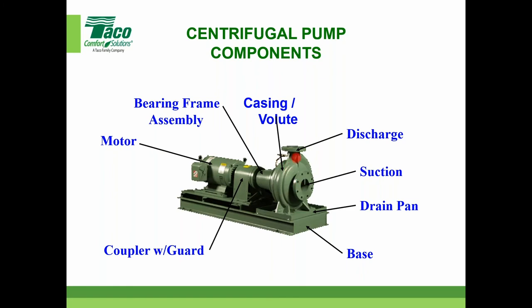And then, hopefully someplace in your specifications, you talk about how, when they do the piping, to pipe away from the pump, don't pipe to the pump. What do I mean by that? Think about a piece of pipe coming down here, right? And there's a long radius elbow and you pipe over to this and there's a flange on the end of that. And now the chances of those two lining up, nuts on, is a little light. So what happens is people use the big screwdriver to force it to line up and tighten up the bolts. Maybe coming down, the same thing, piping coming down horizontal. And sure enough, that's going to put stresses on the pump, could knock it out of alignment, or something bad is going to happen, or it's going to shorten the life, and that's something bad as well.